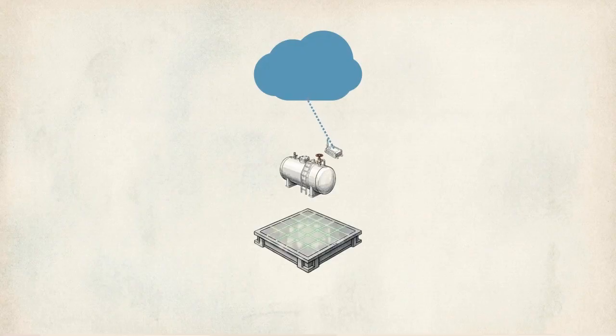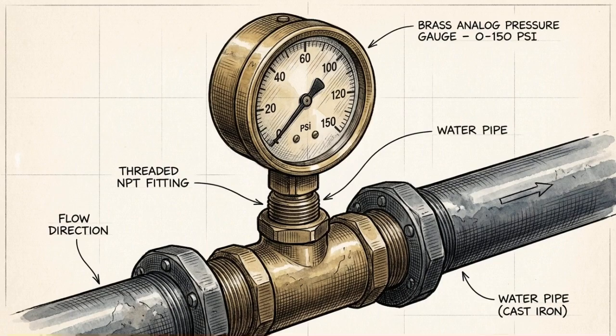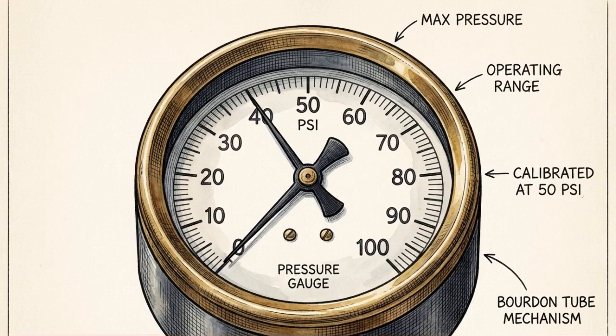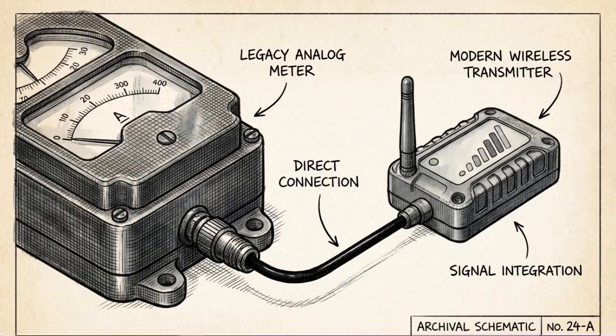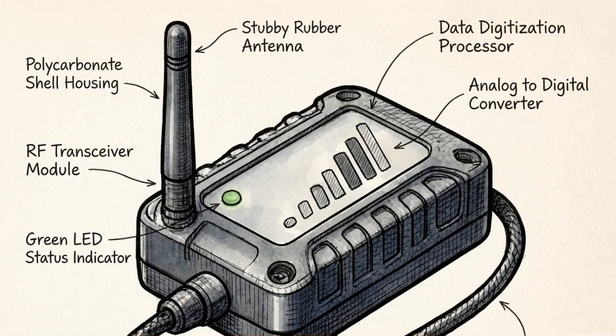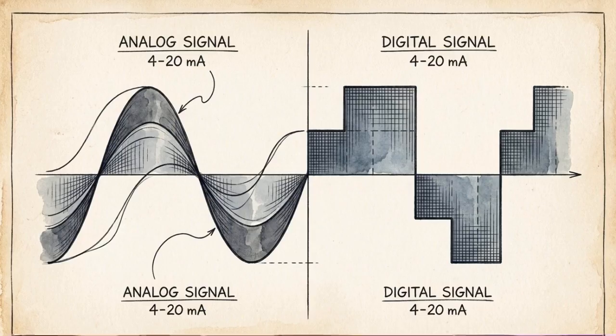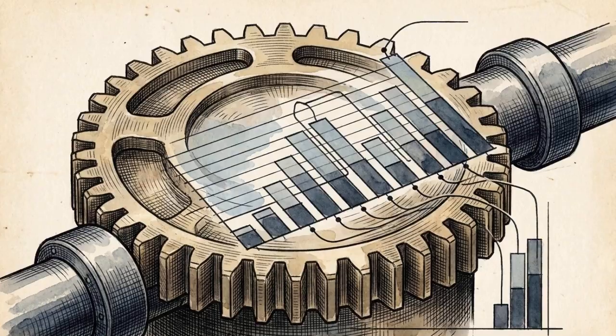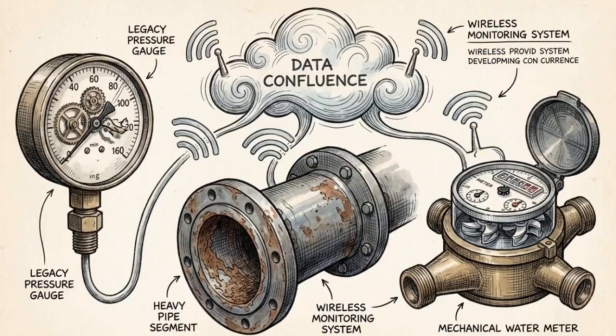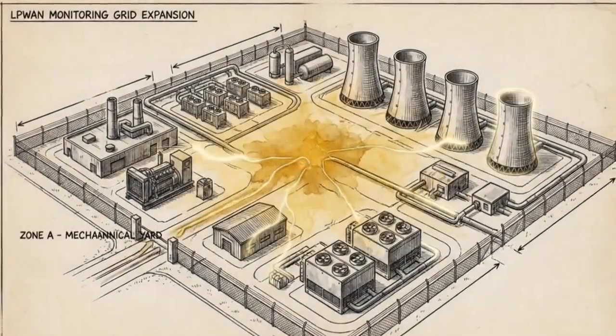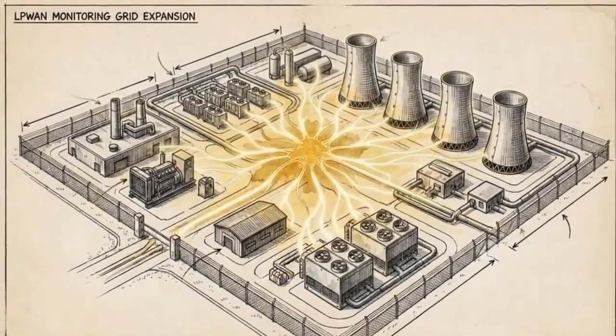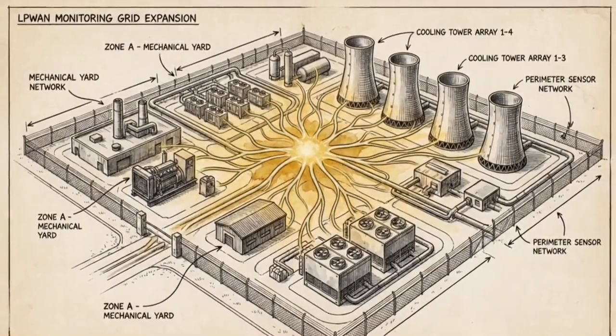When retrofitting an existing facility, operators do not want to tear out perfectly functional analog pressure gauges, water meters, and existing instruments. Instead, they use sensor interfaces. These small transmission nodes wire directly into the legacy hardware. The interfaces instantly digitize standard 4 to 20 milliamp signals, legacy Modbus data, and mechanical pulse outputs, bringing decades-old equipment onto the wireless network. With LPWAN and these sensor interfaces, engineering teams can overlay a modern, continuous monitoring grid onto an existing footprint in days.